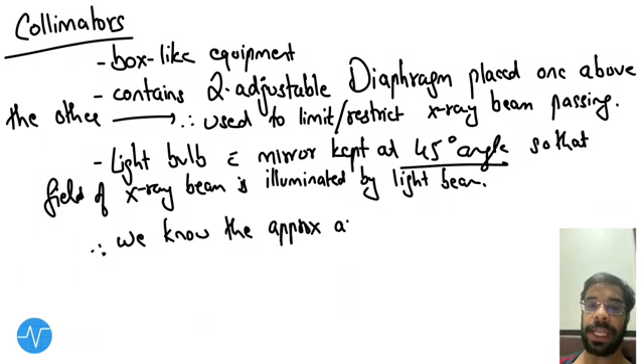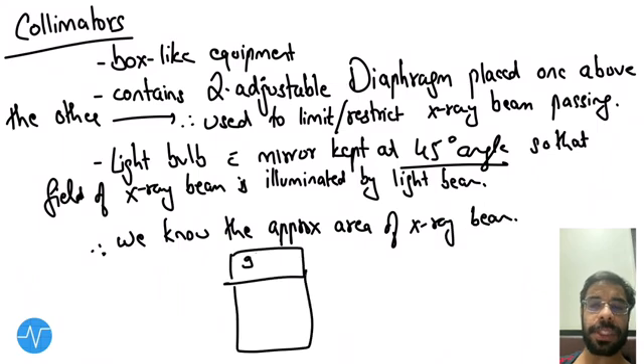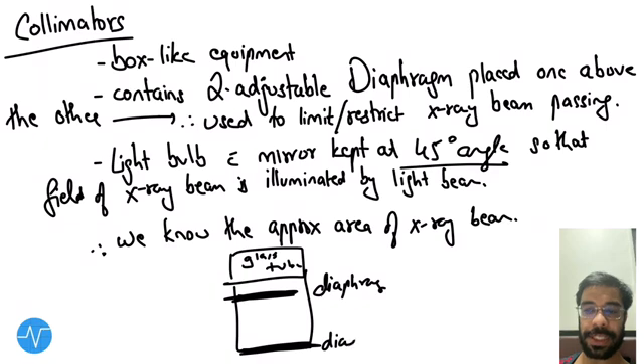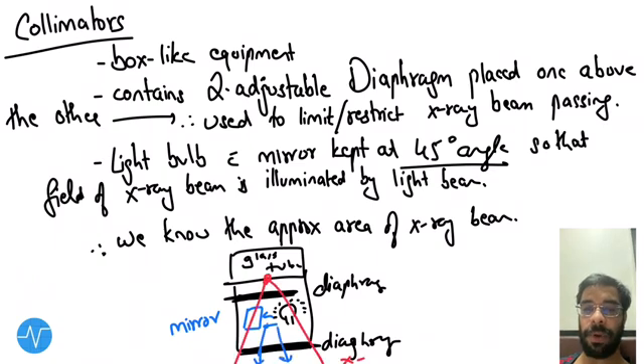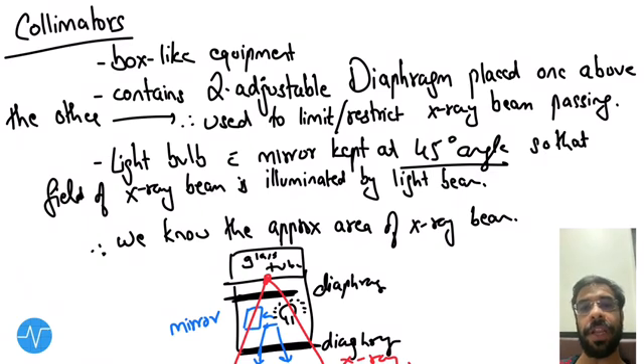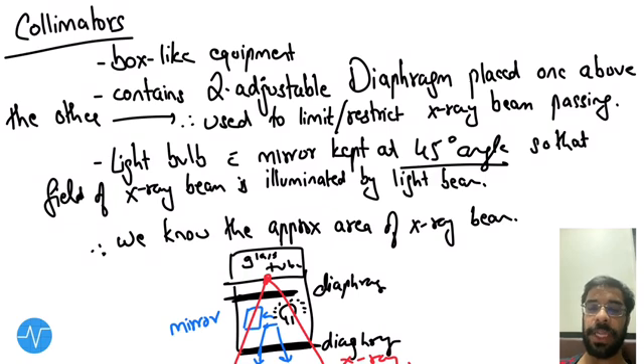By the light, we can determine the approximate area of the x-ray beam. In the diagram: the glass tube is shown with one diaphragm above the other, a light bulb, and a mirror. X-rays and light both emerge, so we can see the range of the x-ray beam because of the light beam.